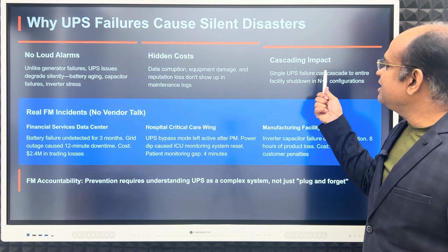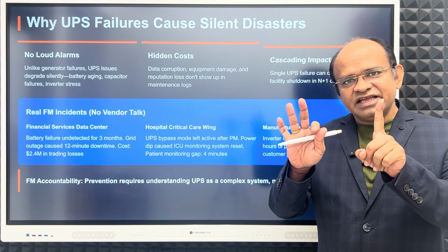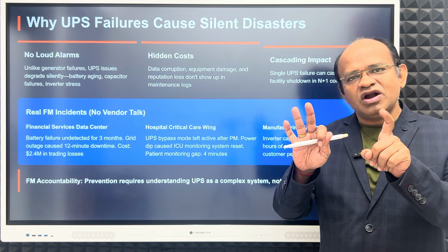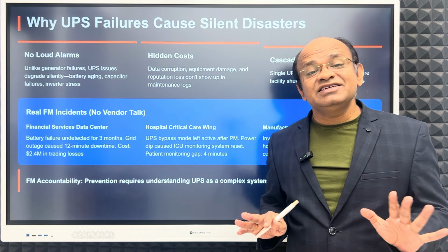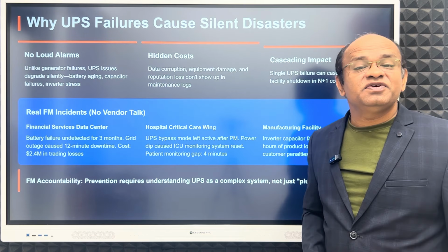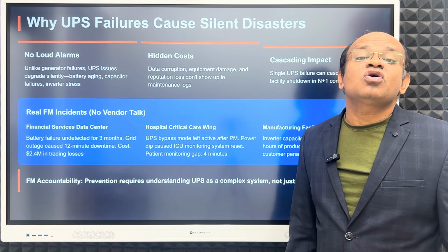How does this happen? N+1 means, let's say 4 UPS units are required to cater to your critical load, then you add 1 more. So N is what's required for the entire load, and this is the extra 1. Whenever one UPS fails, the remaining 3 will not be able to take the entire load. So a single UPS failure can cause cascading failure, the other UPS units get overloaded and they also trip. So it's as if you don't have any UPS at all, single UPS failure can cause failure of all of them.